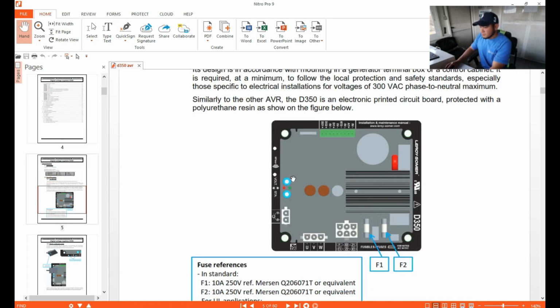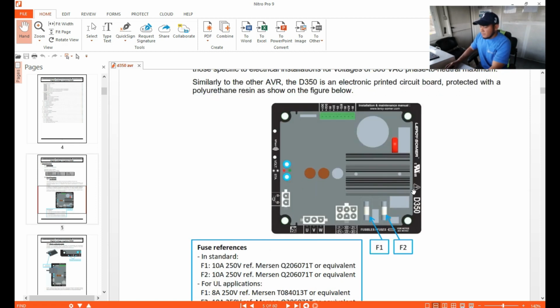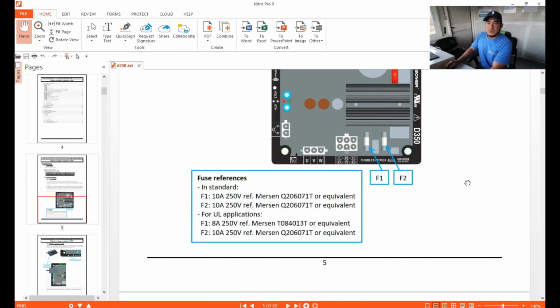As you can see here, we have this kind of AVR, and we have the fusing. We have two fuses here. This is where you can install all the wirings, and let's talk about that one later on. For now, these are the specifications of the fuses you can use in this AVR. The standard is F1 10 amps, equivalent to 250 volts, with a reference Q206071T. F2 is 10 amps 250 volts, and here is 8 amps 250. I'm not sure about these UL applications, maybe Underwriters Laboratories or something like that. And F2 is 10 amps 250.